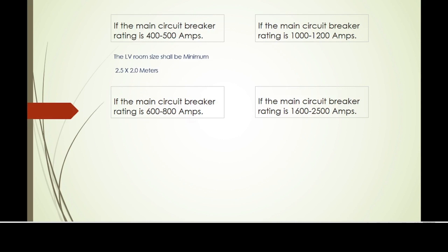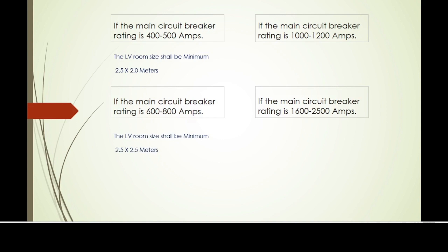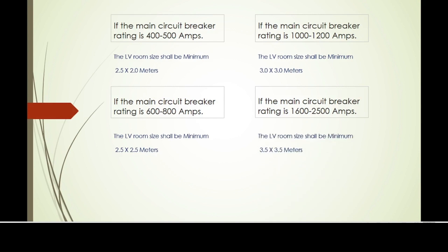If the circuit breaker rating is 600 to 800 amps, then the LV switch room size shall be 2.5 by 2.5 meters. If the circuit breaker size is 1000 to 1200 amps, the room size shall be 3 by 3 meters. And if the main circuit breaker rating is 1600 to 2500 amps, the LV switch room size shall be 3.5 by 3.5 meters.